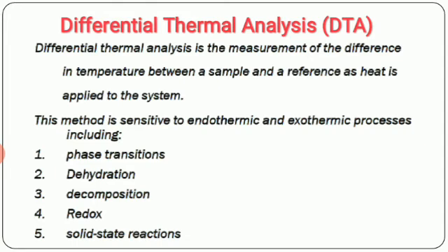Differential thermal analysis. Differential thermal analysis is the measurement of the difference in temperature between the sample and a reference as heat is applied to the system. This method is sensitive to endothermic and exothermic processes including phase transition, dehydration, decomposition, redox, and solid state reactions.